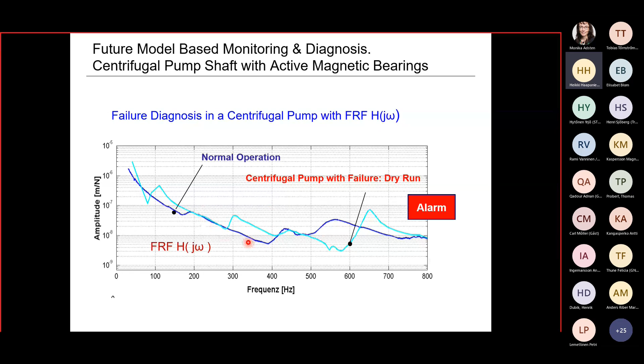And we could see the difference here. This is, of course, an extreme case. Normal operation, dark blue, and dry run here. So that gives an alarm. You have no water in the pump. As I said, this is a very simple example. But you see here the frequency response function, amplitude versus frequency up to 800 Hertz. So we did different other tests where we introduced failures, and we always had some characteristic behavior. How does our system behave?